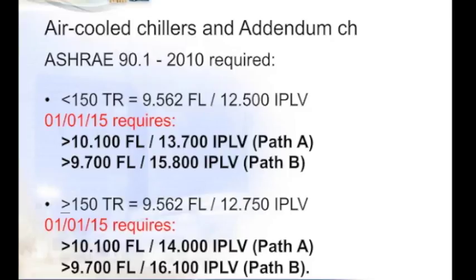The efficiency of chillers 150 tons and larger is as follows. The old requirements were 9.562 full load and 12.75 IPLV. The new requirements for compliance path A are 10.1 full load and 14.0 IPLV. The requirements for compliance with path B are 9.7 full load and 16.1 IPLV. At this point, Pat, why don't you take over and talk about another important item, and that's system balancing.